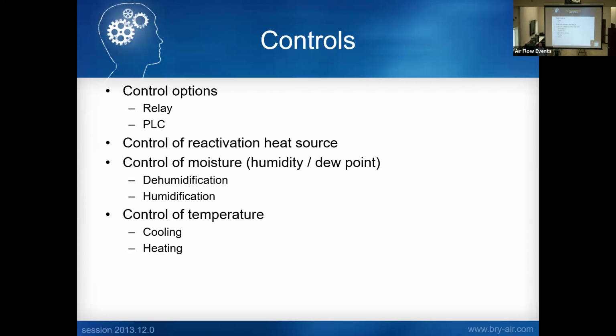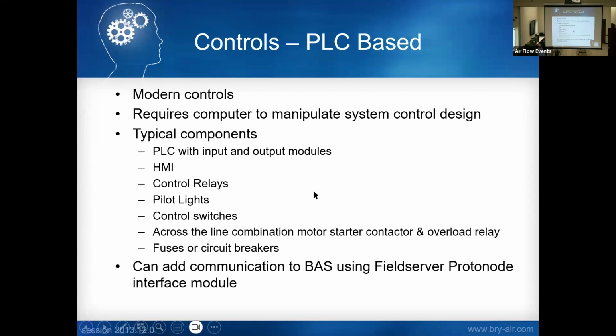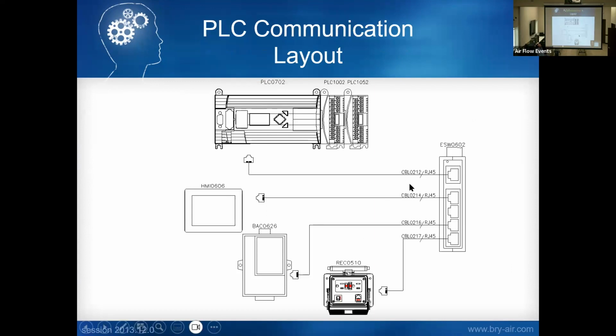Then we control temperature. The temperature could be pre-cooling, post-cooling, or heating, which could be preheating. Again, for bringing in all outside air, you may have to heat the air, or it could be towards heating as well. With the modern PLC controls, we have an HMI on the screen. We do have building automation communication as well, to tie into building automation systems. It's just a typical control layout. We have a PLC and HMI, and a switch inside the unit. On the outside, we have a laptop port with an RJ45 receptacle, so that you can plug your laptop in without opening the control box. And then we have the BACnet module as well.